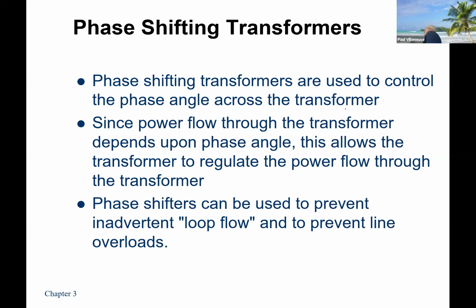Phase shifting transformers are becoming more and more popular. I looked at a bunch of projects in New York over the summer that had phase shifting transformers all over the place. The reason we need phase shifting transformers is that you cannot directly control the flow of real power through a system traditionally, but with phase shifting transformers, you can do that. So you get a lot more refined power control, at a significant cost. Phase shifting transformers are about 5 times more expensive than regular no load tap changing transformers. They're becoming more common because the grid has been changing a lot. Like I said, there's a bunch of them proposed for New York, but they have some real challenges with them. Okay.